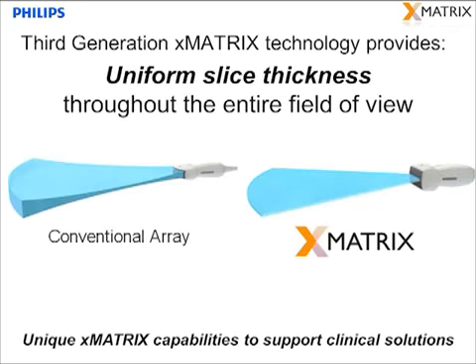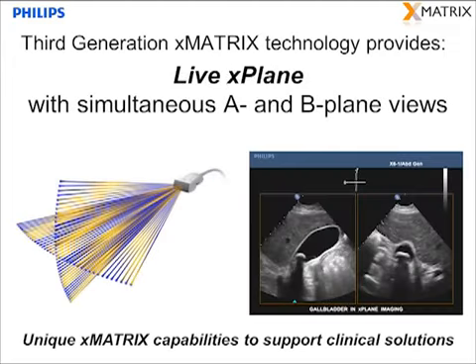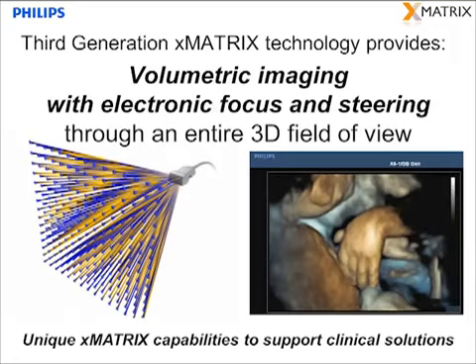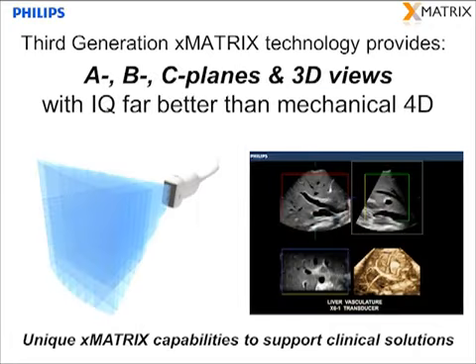Uniform slice thickness reduces clutter and improves image quality throughout the entire field of view, even when looking at a standard 2D image. Live X-plane allows viewing of two live images simultaneously with high frame rates and control of the location of the imaging planes within the field of view. Live 3D allows imaging of an entire volume with electronic steering and focusing throughout the entire field of view. We also have MPR views with A, B, and C planes as well as 3D with image quality that's far better than a mechanical transducer, especially in the C planes. The slice thickness control means that we can look at any plane within the volume with great image quality.